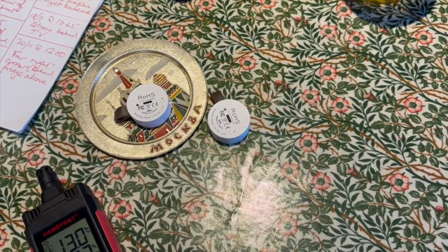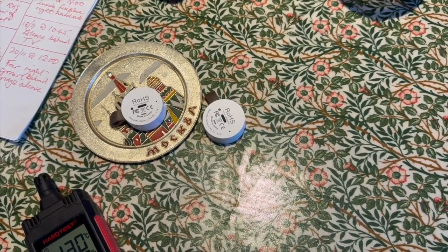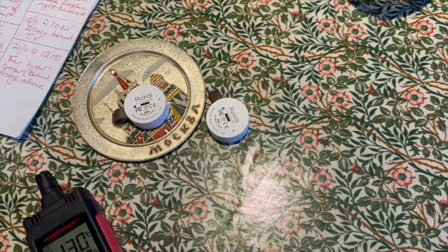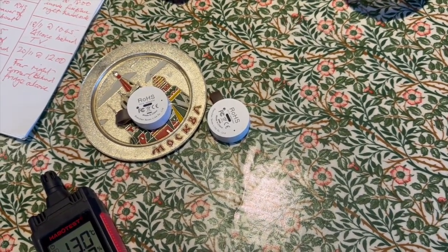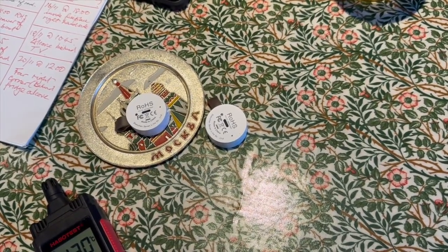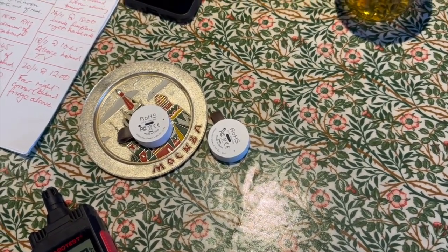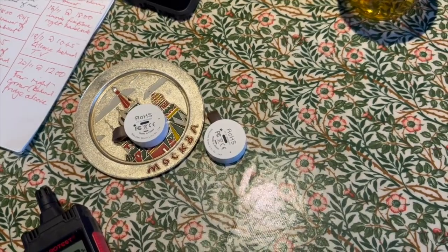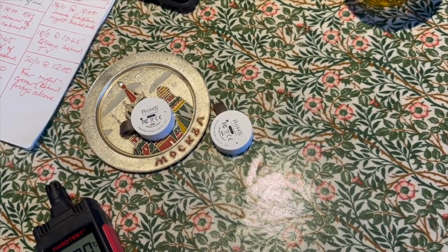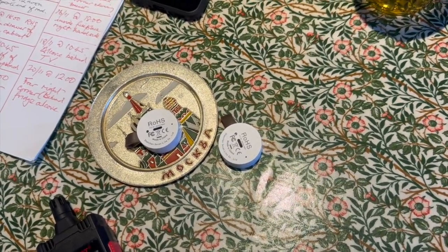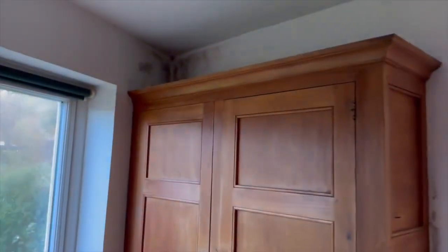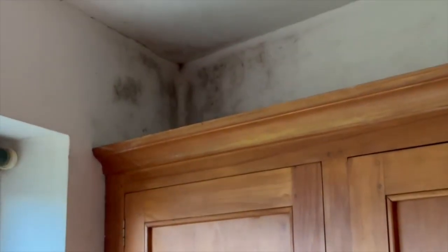Mould only grows when relative humidity goes above 85% for long periods of time, sort of 8-10 hours at a time. You will get mould growing in three zones. One where there's excess vapour, so where the internal dew point is greater than the outside temperature. Two, where there's poor airflow, so into a corner like that, where you're getting very little airflow from the radiator.